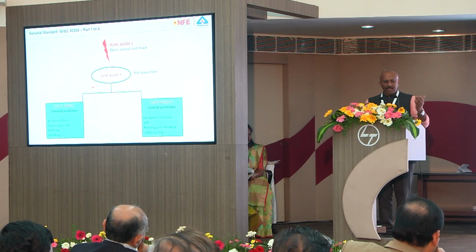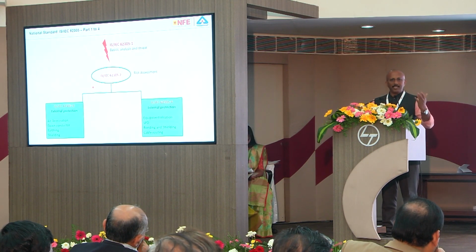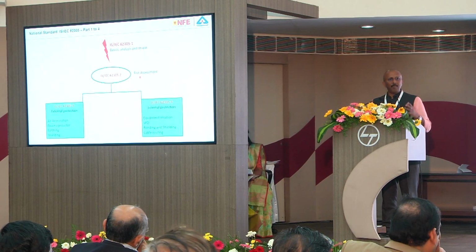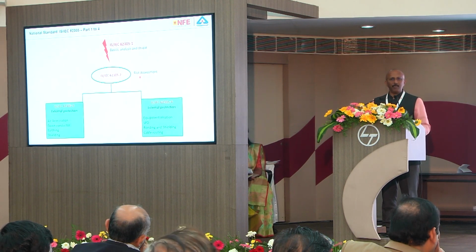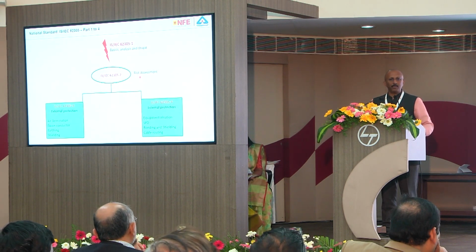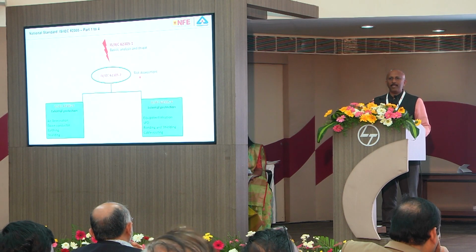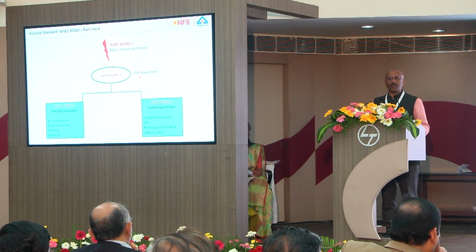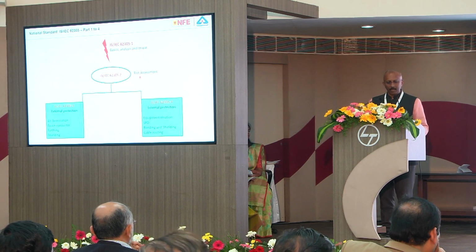So basically, the risk assessment, of course, is an important subject, but don't try to make it the most important subject. I would say the most important subject is, for example, you have a building which has to exist for the next 50 years or 100 years. You have to make an installation which has to exist at least for 25 years. So the selection of material, the corrosion, the tightening torque, those are much more important than the risk assessment. Now, coming back.